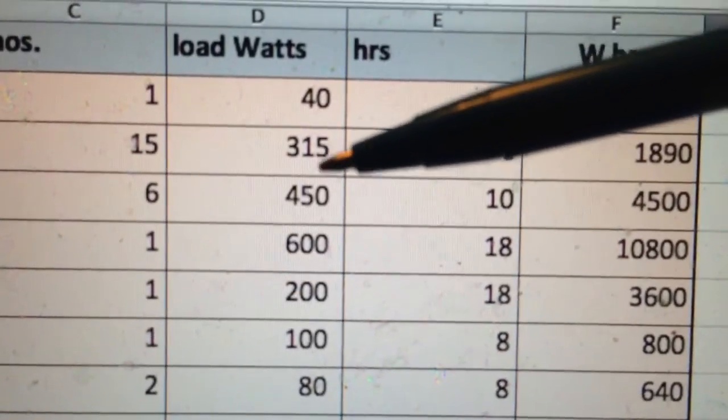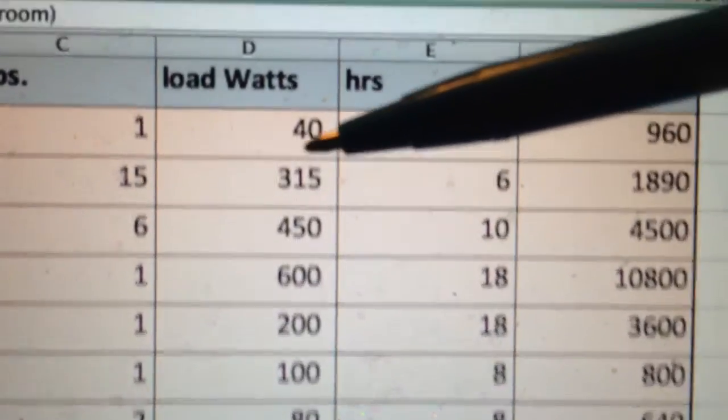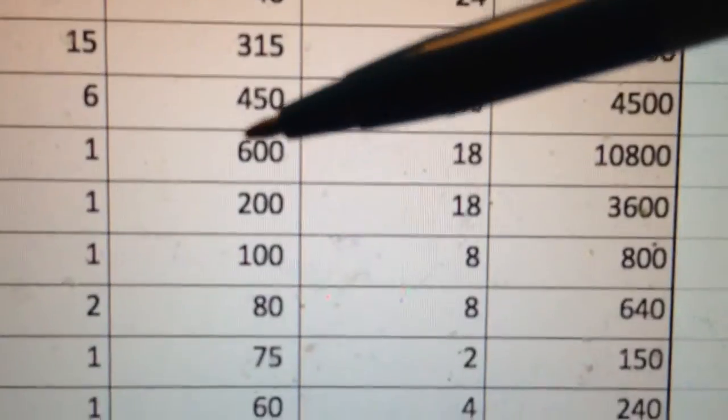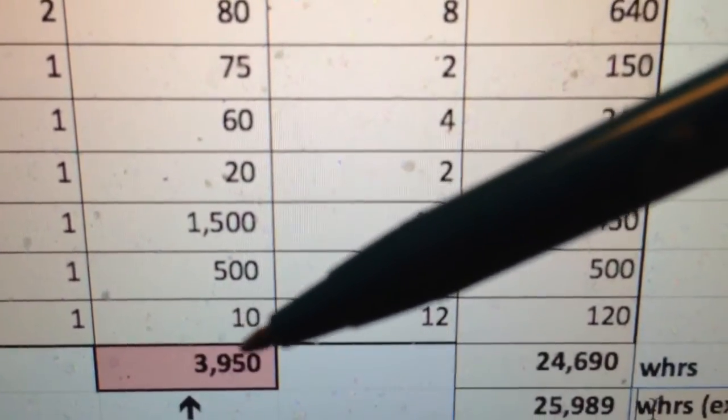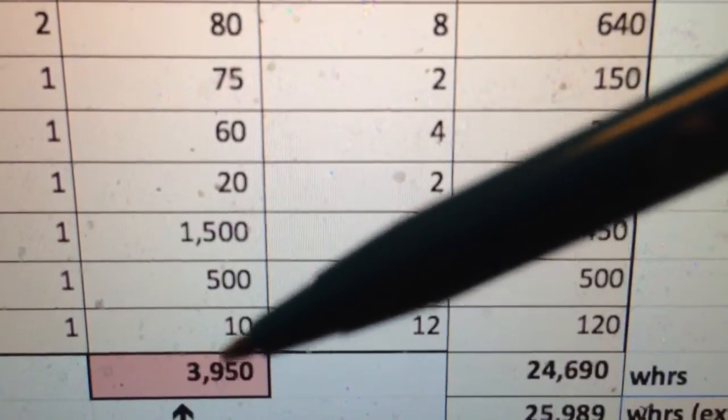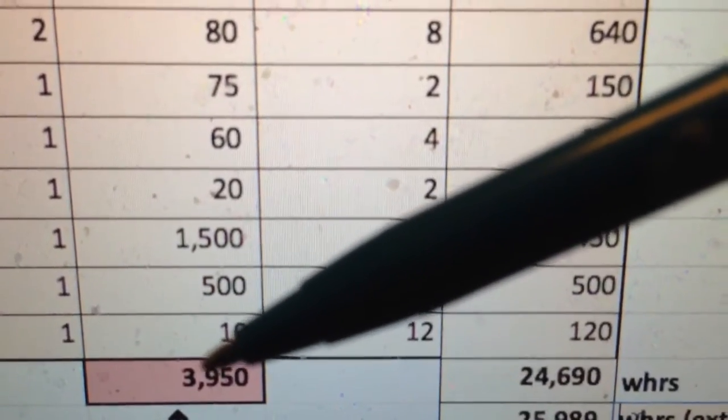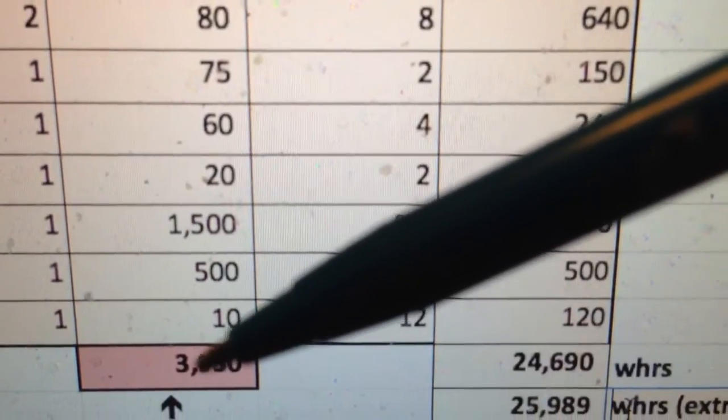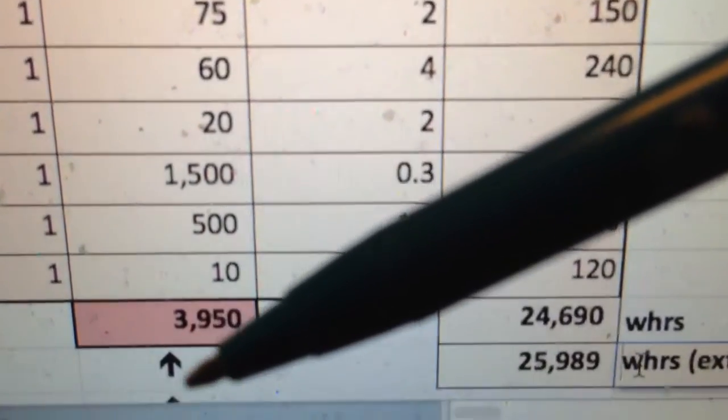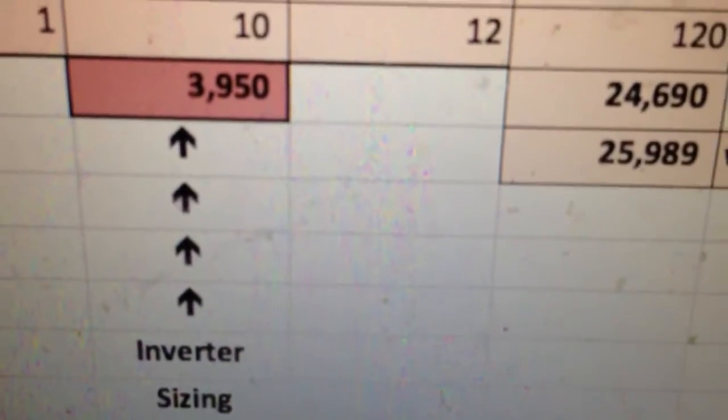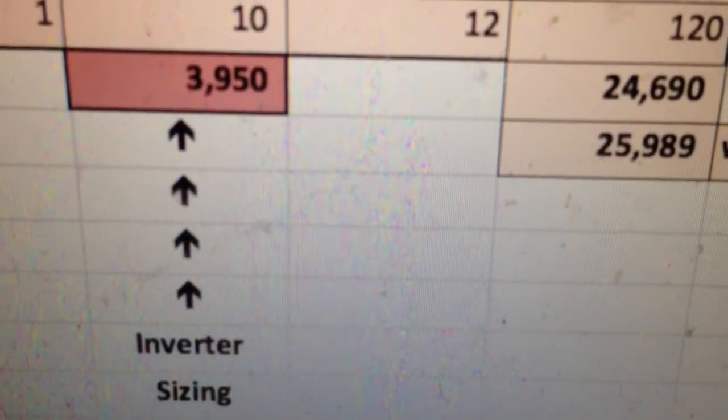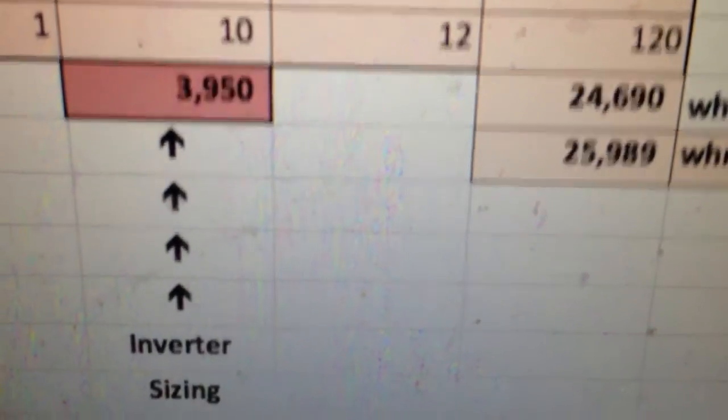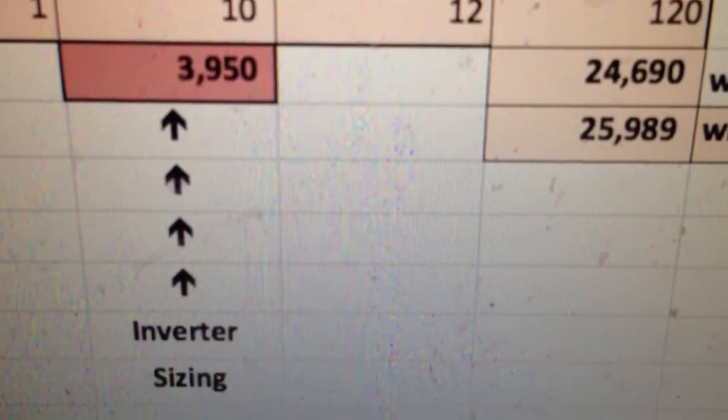So in any given instant, all these things all turned on together at the same time will give us 3950 watts. That is your load: 3.9 kilowatts. And this number is very, very important for when we're talking about inverter sizing. So this exercise is good to know how many panels you need, how many batteries you will need, what kind of system you'll need, as well as actually how big an inverter do you need.